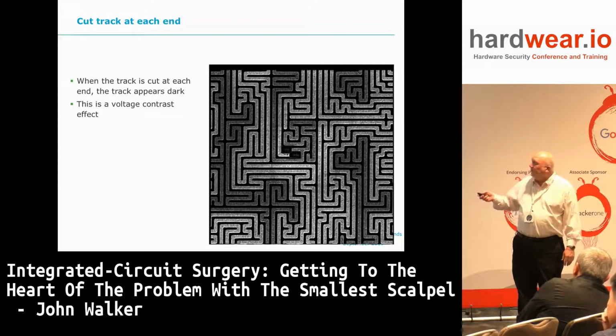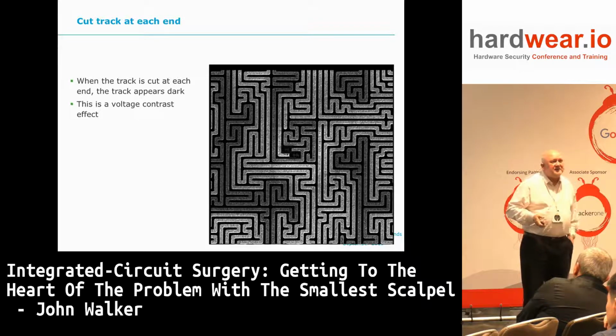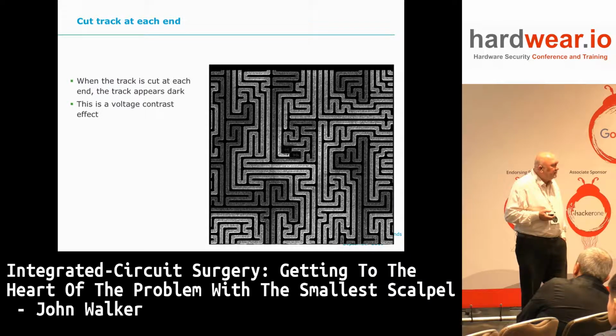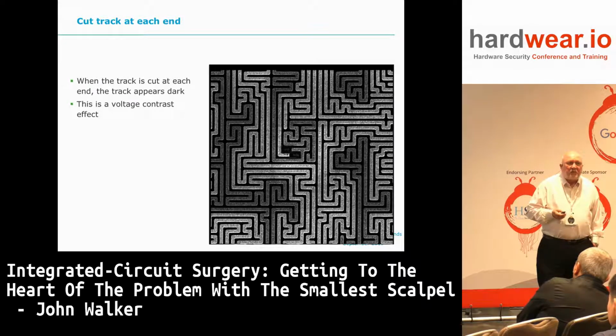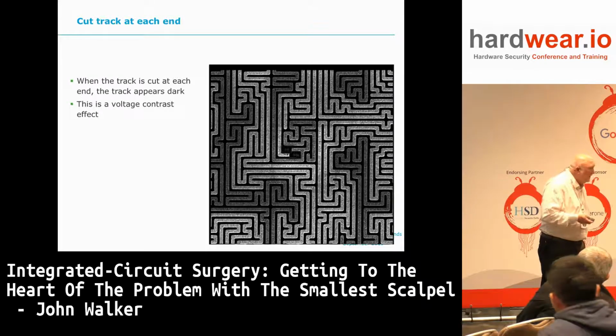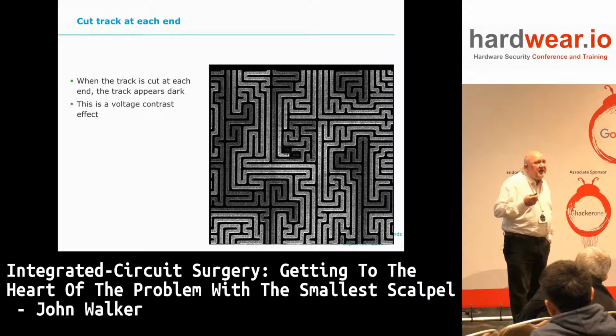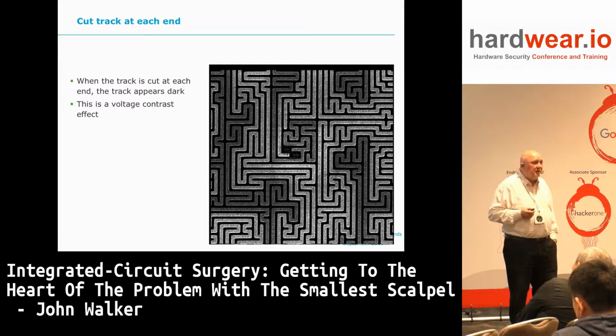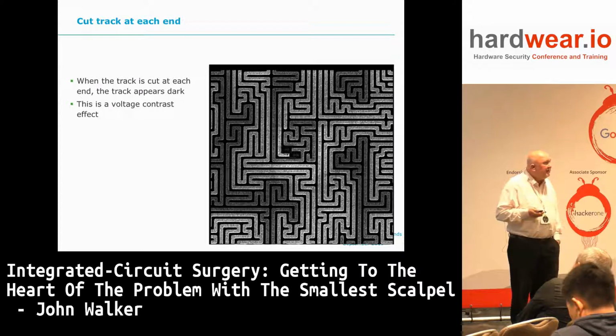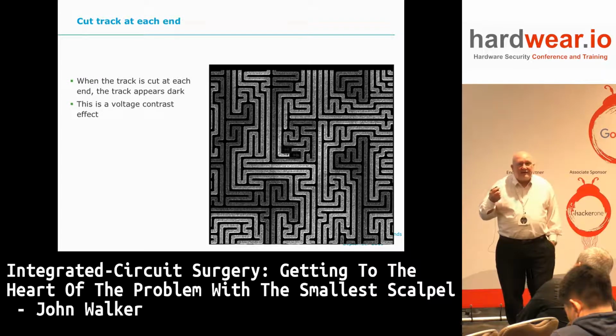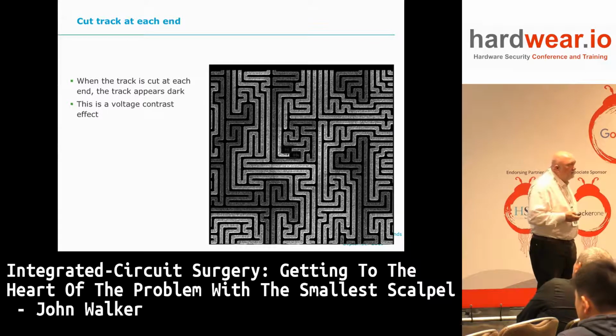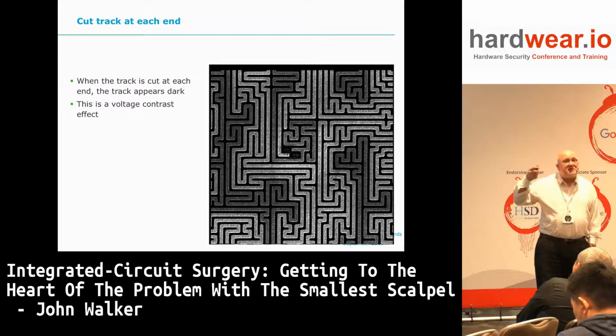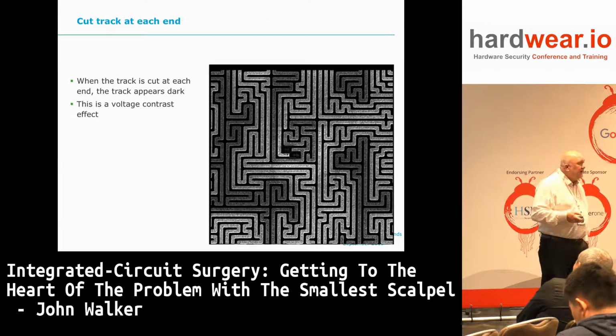And now look what's happened in the circuit lines. You can see there's two different shades of the track in that circuit. What's happening here? This is an effect we call voltage contrast. So when the electrons, or ions if you're using a focused ion beam to do it, hit a track, if that track is disconnected by cutting it from anywhere else, it is not connected to ground, and it can float up to any potential, any voltage that the ion beam or electron beam is imparting to it. And in this case, if it charges up positively, then what will happen is that the electrons which would like to escape from there can't escape from there. They get sucked back into that area, and the whole thing appears dark.